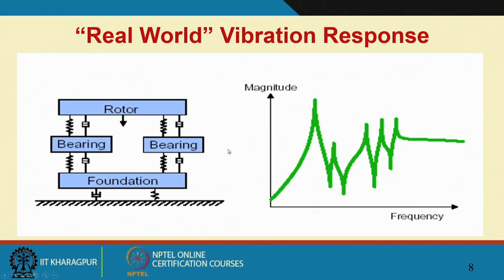In practical real-world examples, a rotor is a shaft carrying a disc supported on two bearings anchored to a foundation. The frequency response from a transducer on the bearings shows many natural frequencies. Every frequency corresponds to a mechanical element in the machine. If a corresponding element has gone wrong, amplitudes at those frequencies change — that is the genesis of why CBM using vibration monitoring is so popular.